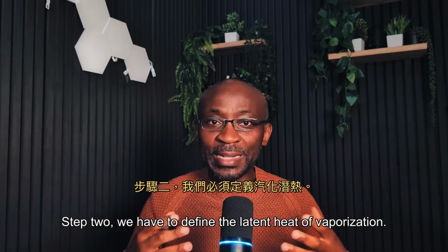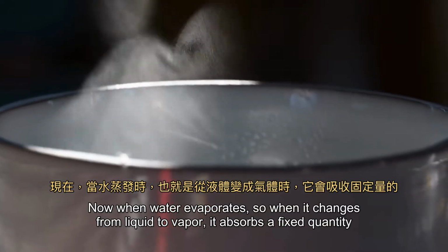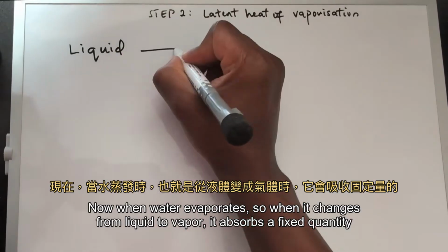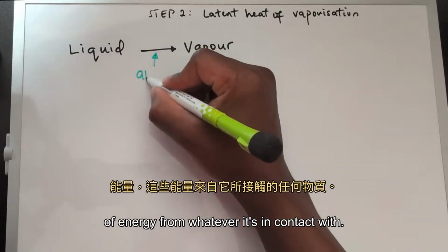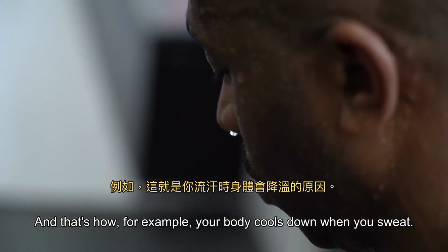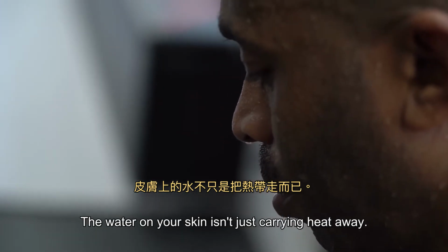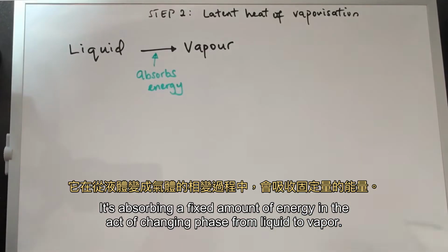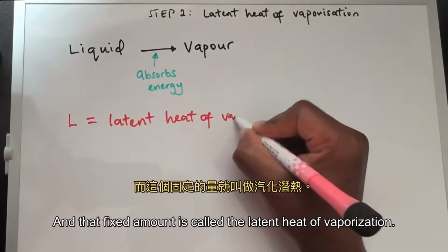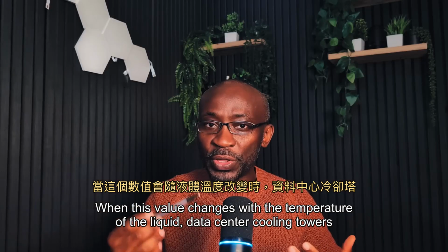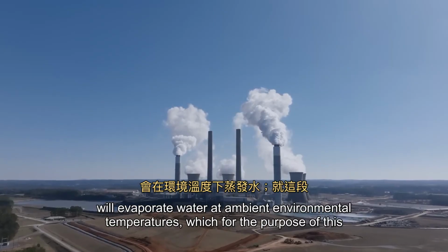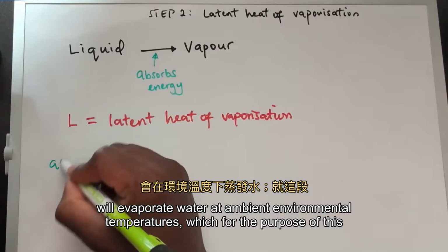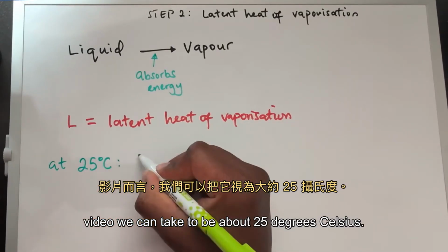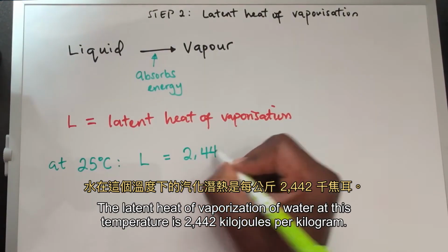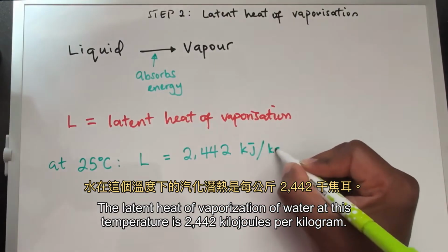Step two, we have to define the latent heat of vaporization. Now, when water evaporates, so when it changes from liquid to vapor, it absorbs a fixed quantity of energy from whatever it's in contact with. And that's how, for example, your body cools down when you sweat. The water on your skin isn't just carrying heat away, it's absorbing a fixed amount of energy in the act of changing phase from liquid to vapor. And that fixed amount is called the latent heat of vaporization. And this value changes with the temperature of the liquid. Data center cooling towers will evaporate water at ambient environmental temperatures, which for the purpose of this video, we can take to be about 25 degrees Celsius. The latent heat of vaporization of water at this temperature is 2,442 kilojoules per kilogram.